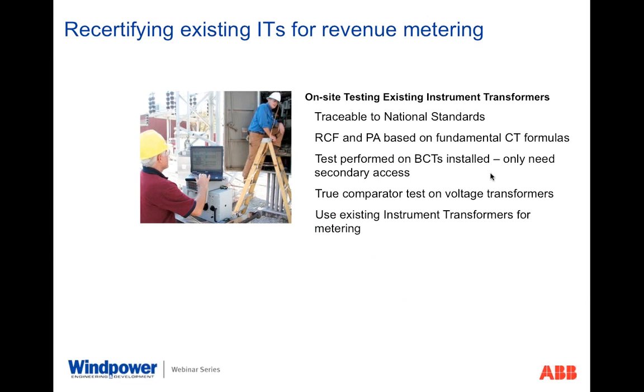Now, one last point I'd like to make about accuracy is the ability of trying to convert existing installed instrument transformers into certified accuracy devices for metering. There are capabilities out there today where you can do on-site testing to basically recertify a CT, in many cases a relay type CT, for use as a revenue metering CT. So we have a methodology that we bring to bear to be able to provide RCF and phase angle accuracy information based upon fundamental formulas on the CT designs and the VT designs. We provide that capability to test that unit on site without removing them from service, de-energized, mind you, but do not have to take them out of the installation that they're based in.